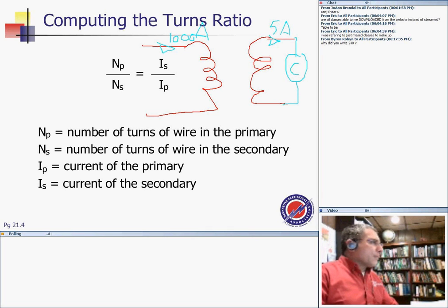I can't put 1,000 amps across my coil and stay in business. So this way, the turns ratio, guys: we take the 1,000 on the primary. The turns ratio, where the secondary is 5, divided by the primary, 1,000. So 5 divided by 1,000, or 1,000 divided by 5. I'm losing my mind here. 200.